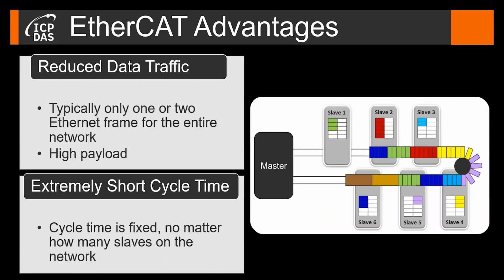EtherCAT is optimized for reduced data traffic. A traditional EtherCAT network consists of a master controller along with multiple slave devices connected to the master using an Ethernet cable. Typically, only one EtherCAT frame per cycle is needed to exchange data with all the slaves in the entire network. Each cycle, a single telegram is passed by the EtherCAT master with the data of all nodes. The telegram is passed around a ring where each node exchanges data with the telegram, and it returns back to the master when the last slave receives the telegram. This means in each cycle, with just one frame, each slave is updated with new output data from the master and the master receives new input data from all slaves. So the low data traffic enables extremely short cycle time for the EtherCAT network. In addition, cycle time is fixed, however many slaves are on the network.